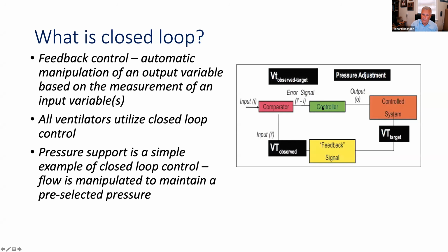I have the machine try to deliver that input. In this case, we're looking at tidal volume. I measure the tidal volume, and again, it's usually tidal volume that's delivered from the ventilator, not exhaled. And I compare what I want versus what I got, look at the difference, and I try to make the difference 0.